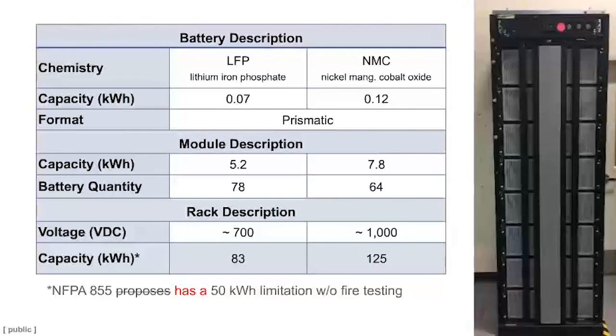When you take all these modules and put them together in series, the voltage can really add up. The iron phosphate voltage, if fully connected, is around 700 volts, and the NMC is about 1,000 volts. So that's just in terms of electrical safety. When you look at the capacity of the systems, it's important to detail that the iron phosphate system was 83 kilowatt hours, and the NMC was 125 kilowatt hours. So even though I'm going to show you large-scale results for both of these, it's not a 100% apples-to-apples comparison because I'm not testing the same energy capacity.